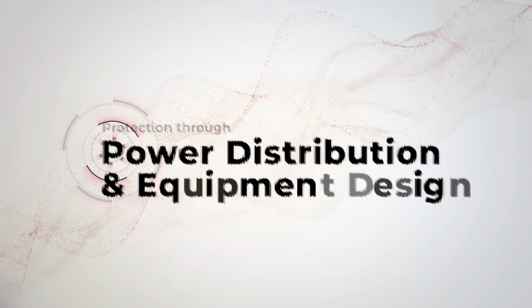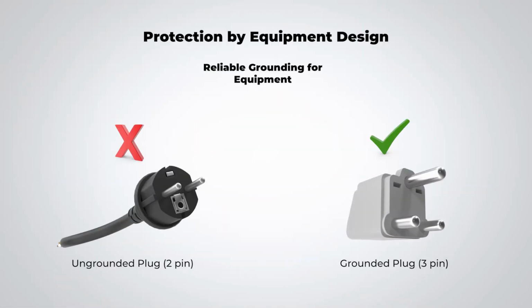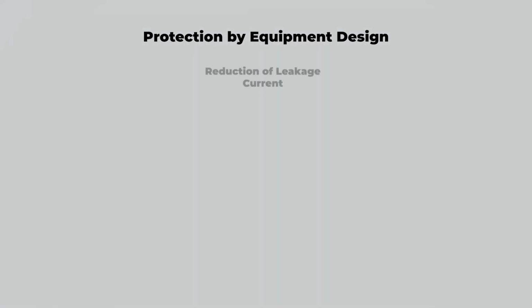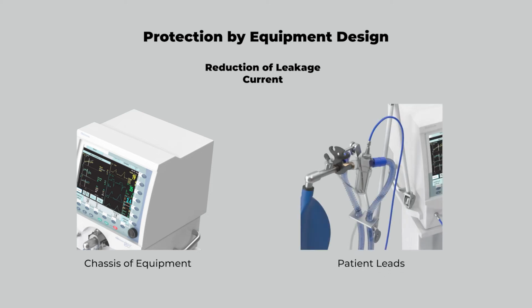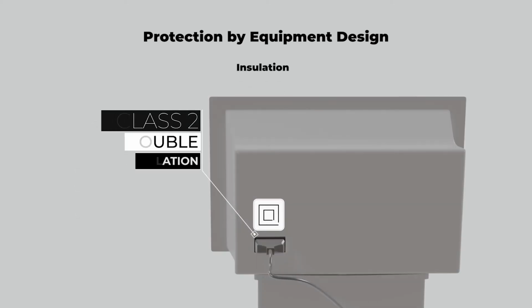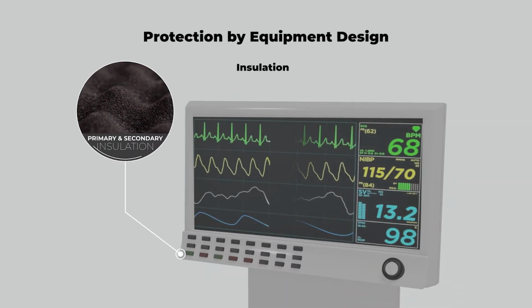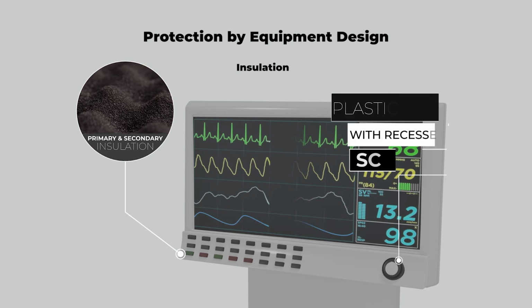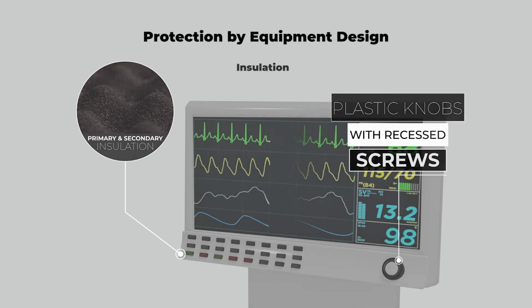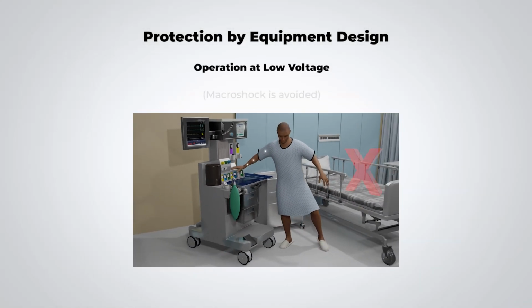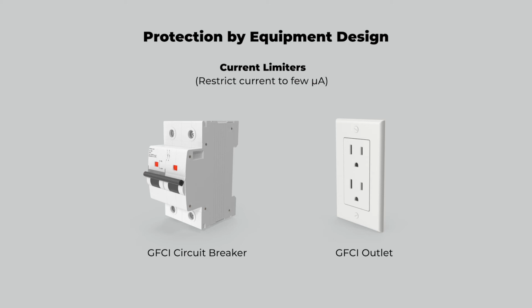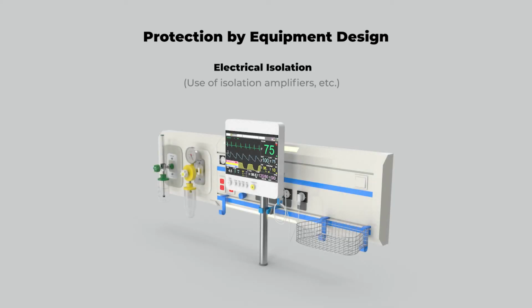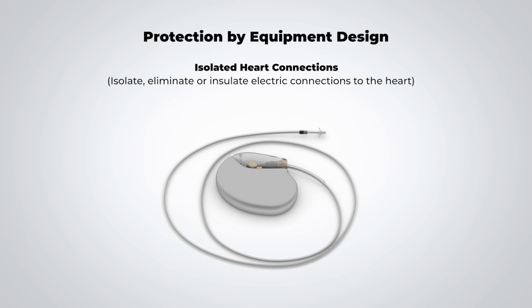Protection by equipment design entails the following. Reliable grounding for equipment. Reduction of leakage current in chassis of equipment and in patient leads. Double insulated equipment. Primary and secondary insulation between chassis and outer case, plastic knobs with recessed screws. Operation at low voltage, so macroshock is avoided. Current limiters restrict current to a few microampere. Electrical isolation, use of isolation amplifiers, etc. Isolated heart connections, to isolate, eliminate, or insulate electric connections to the heart, for example in external heart pacemakers.